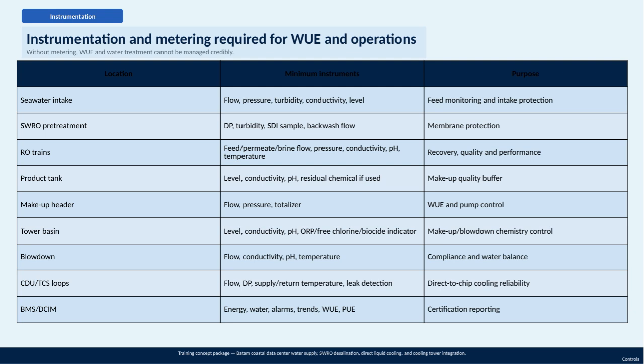At the makeup header, flow, pressure, and totalizer data are important for controlling water use efficiency and pump operations. In the cooling tower basin, parameters like level, conductivity, pH, and indicators for sanitizers such as ORP, free chlorine, or biocide help manage water chemistry for blowdown and makeup cycles. The blowdown monitoring uses flow, conductivity, pH, and temperature to ensure compliance with regulations and maintain the water balance. In the CDU and TCS cooling loops, monitoring flow, differential pressure, supply and return temperatures, and leak detection are crucial to maintaining reliable direct-to-chip cooling.